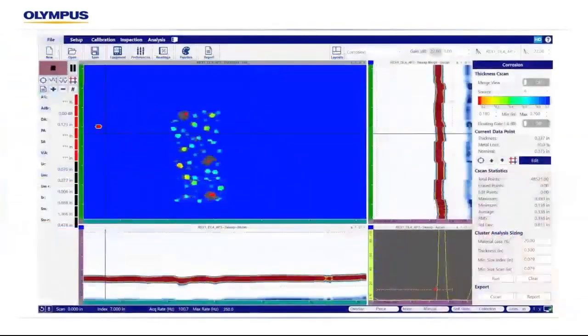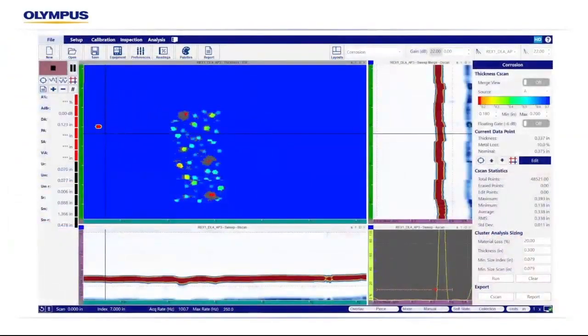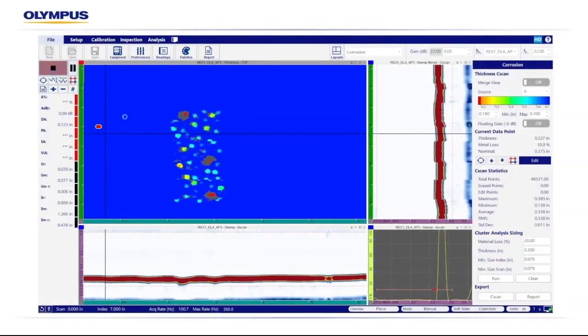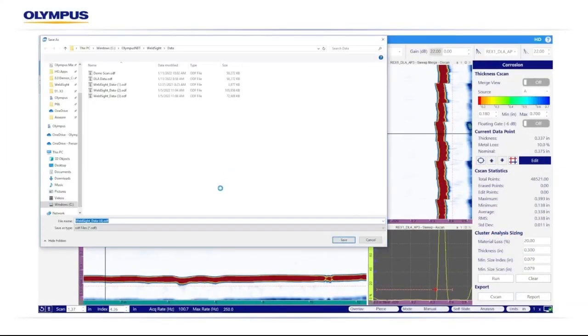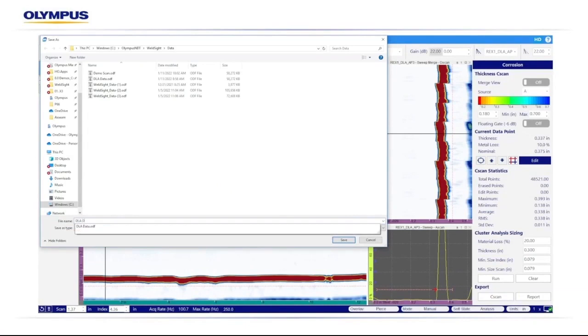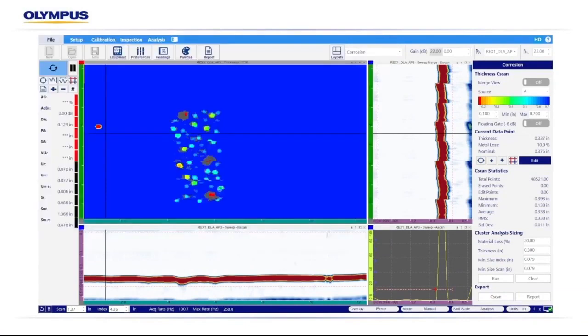To complete the scan, we'll select the stop icon to save the file to our desired file name and location. Once saved, we'll default to our analysis mode, where you can see the corrosion manager on the right-hand side of the screen.